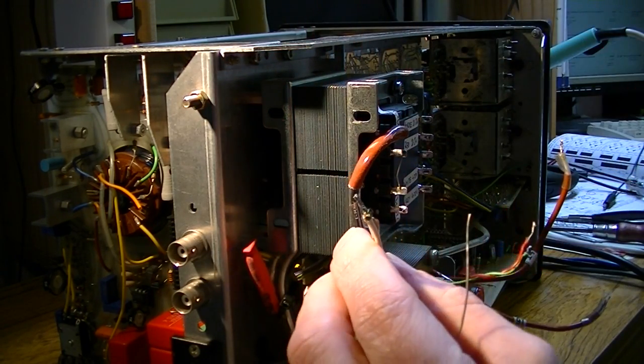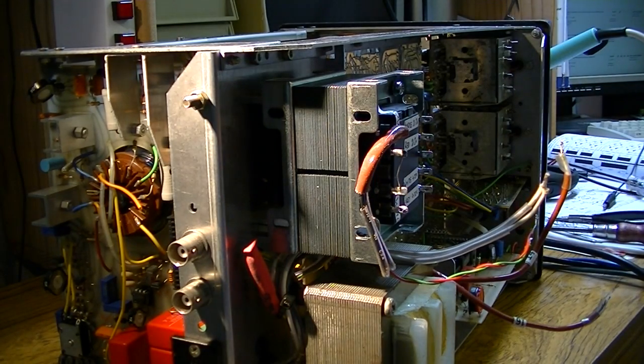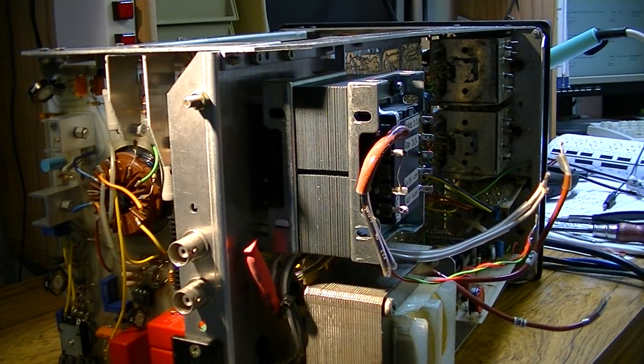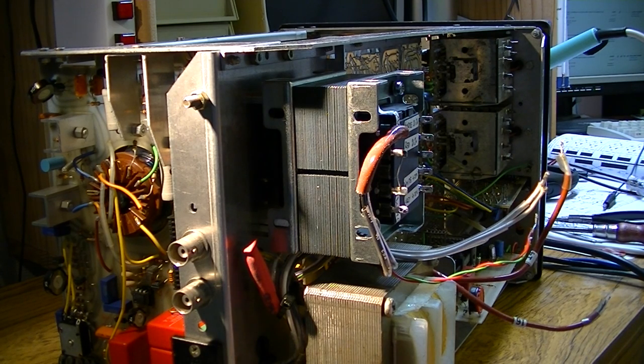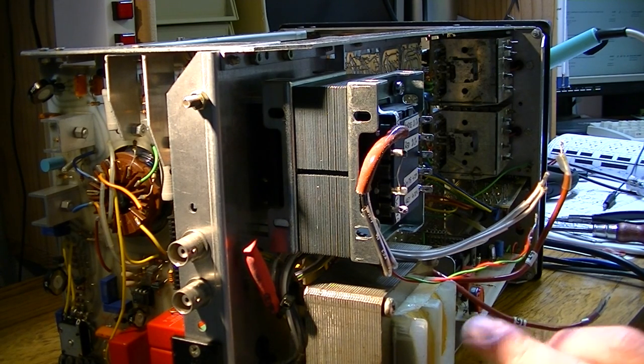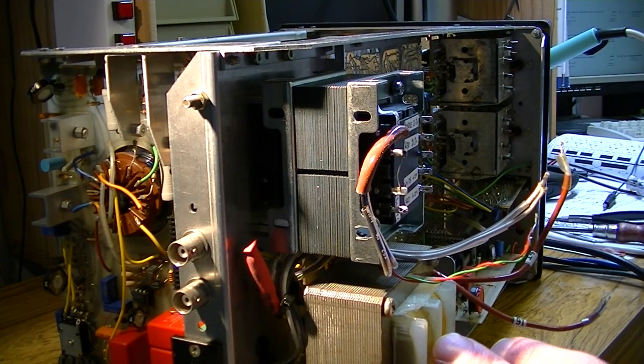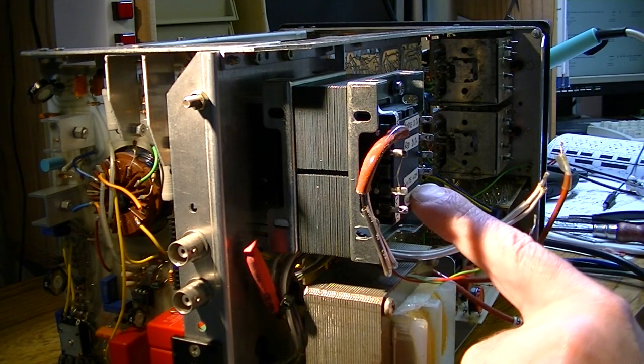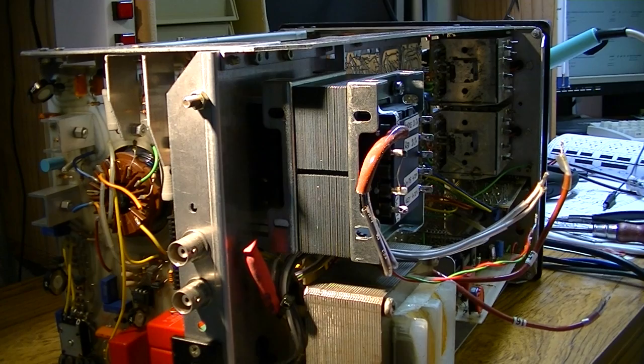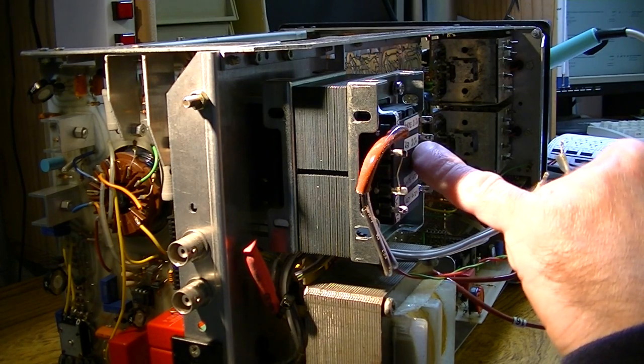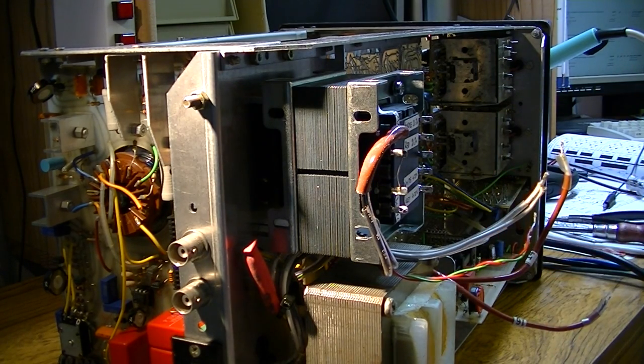It's important to wire - I know it's AC, but the wires need to go on in the correct order to make sure the phase of the output matches the phase for these windings, because although the 470 volt output is fairly well isolated, the 31.3 volt output works in series with some of the windings on the existing transformer, so it's important that the phase is the right way around.